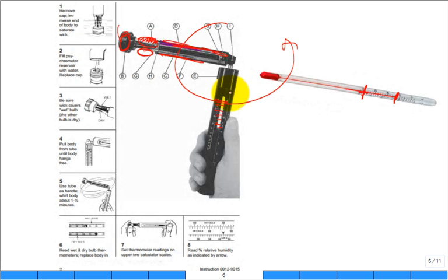When do you think you would walk into a room, sling it around, and the wet bulb would have the same temperature as the dry bulb? 100% saturated. Very good. Here in Houston, after a rain shower, it's 100% relative humidity. It's saturated air, and there's no evaporation potential. And so there's no evaporative cooling on that wet bulb.